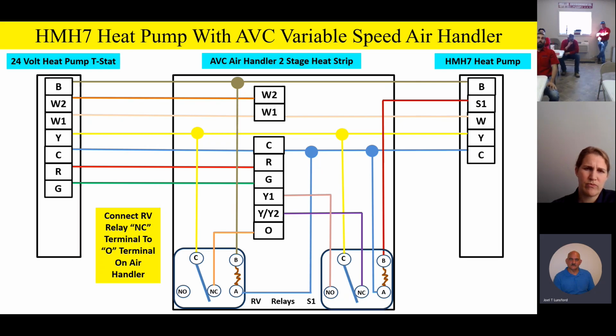So right now, as we take a look at that, if I switch the thermostat on in the cooling mode, it's going to energize Y. It'll turn the outdoor unit on. The outdoor unit says, "Ooh, I've got a compressor call, but I do not have a B signal for heating." So I know I'm in cooling mode by default. And so the unit, as you're looking at it right now, is in the cooling mode, high speed airflow.